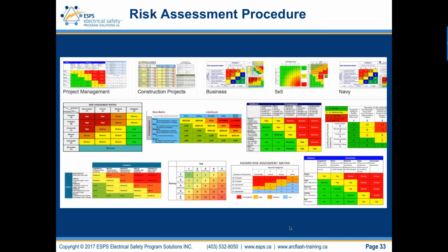So again, I encourage you to review what you've done or maybe haven't done with respect to the risk assessment procedure. And if you need some help in this area, ESPS has resources and we can help give you the information you need, work with you to understand what this is, and have a process that's not complicated. At the end of the day, this maybe looks complicated or it looks overwhelming initially. But once you review it and understand the context of it, and that this is a tool to make decisions and it's a very good tool, it will help us better manage arcing fault and arc flash and understanding the probability. And in turn, shock, once you do address shock, is relatively simple from the perspective of reducing the residual risk.